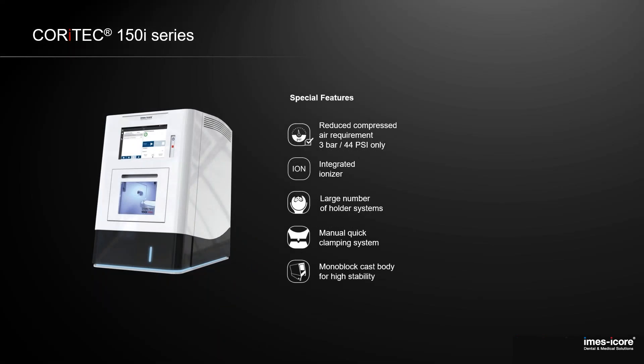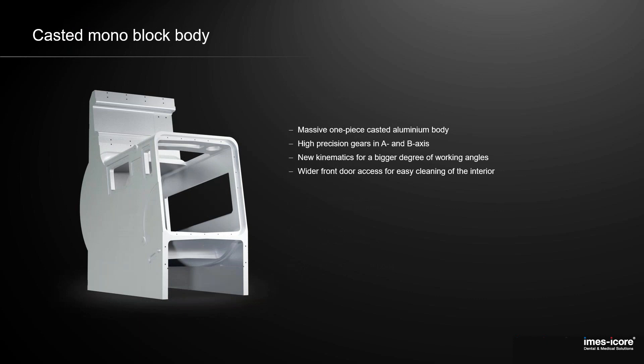The stability we need is made for high precision and the standard materials we use to mill — zirconia, PMMA, and blocks. But as we are now going to mill metal with this machine as well, we are using a casted monoblock body made out of aluminium. It's only one piece, there are no joints, no movement, no bending — it's really smooth during milling. We also increased the precision of the A and B axis gears. So the machine is extremely stable for all materials and wet and dry milling.